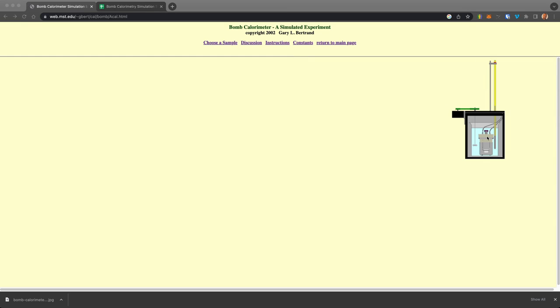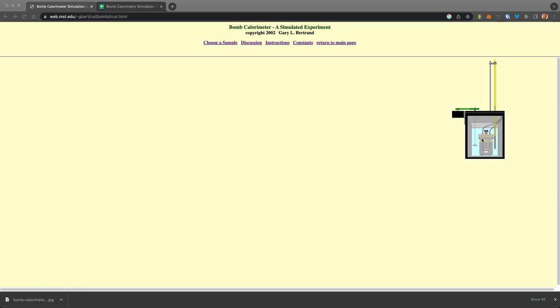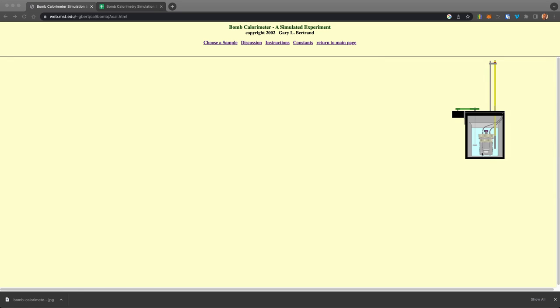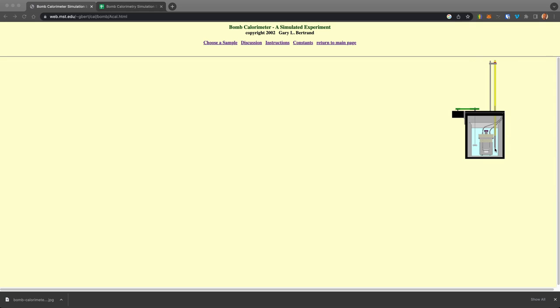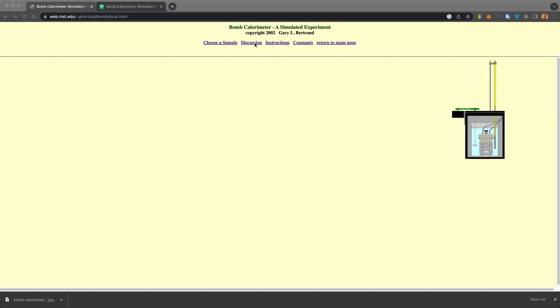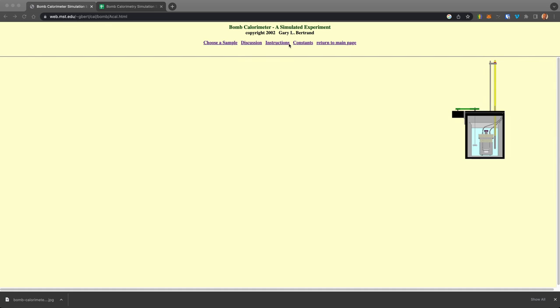And they show a kind of a cartoon schematic of what I just described, where you have your sample in here. You ignite it in an atmosphere of oxygen, and then you watch the temperature change. And they give very detailed discussion and instructions for how to use this and the constants.